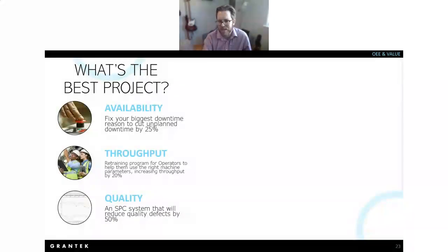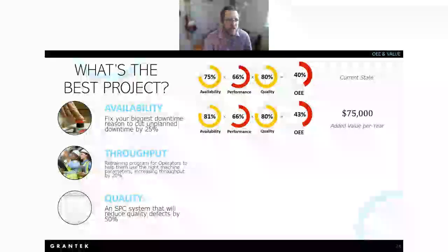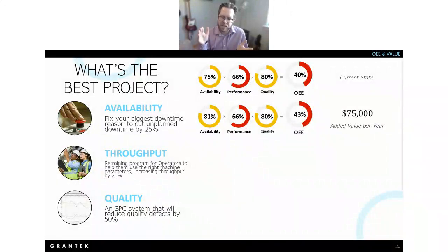So with that context, let's start to look at those projects again. What is the best project? That availability one, the throughput, or quality? So we have our baseline OEE at 40%. If I go and cut that 25% of the time that I'm down by another 25%, it puts us at about 81% availability, which increases my OEE by 3 points, or about $75,000 a year.